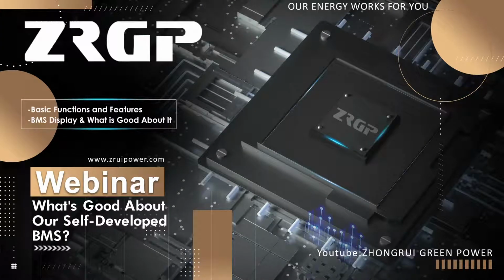BMS has total voltage monitoring, cell voltage monitoring, battery temperature monitoring, charge and discharge current acquisition, equalization control, charge and discharge control, short circuit protection and voltage and current overcharge and over-discharge protection, current limiting and constant current charging, heating film control, pre-charging circuit, storage and clock control, CAN 2.0B communication, RS485 communication, RS232 as well, and other functions. Users can flexibly combine and configure according to actual project applications.